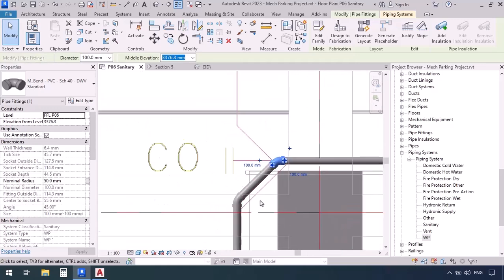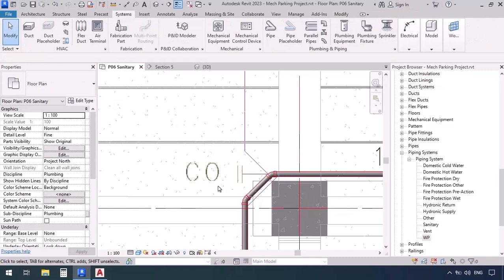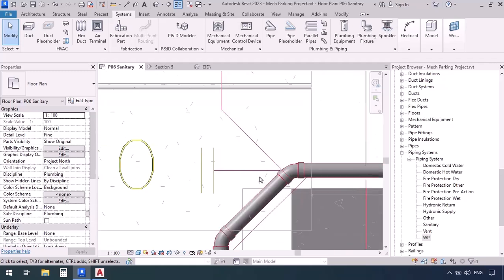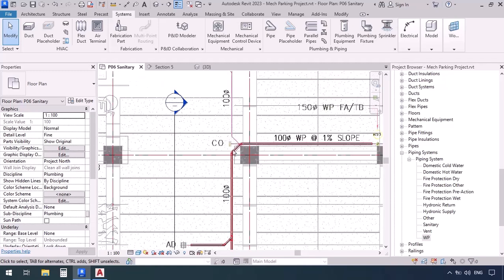Now we want to continue drawing the rest. Here, for the drain pipes, we never use crosses — we have no such thing as a cross. So now we have to place two consecutive T's to draw the junctions on this side. Another point to consider is that we're going to continue drawing according to the plan.